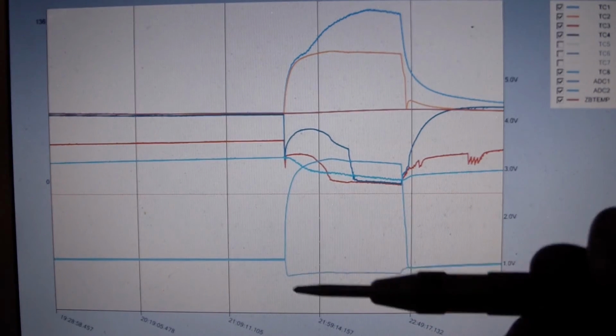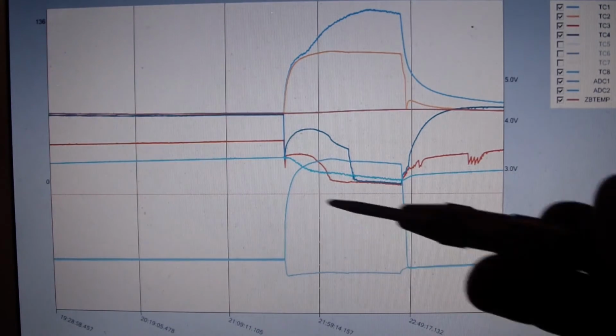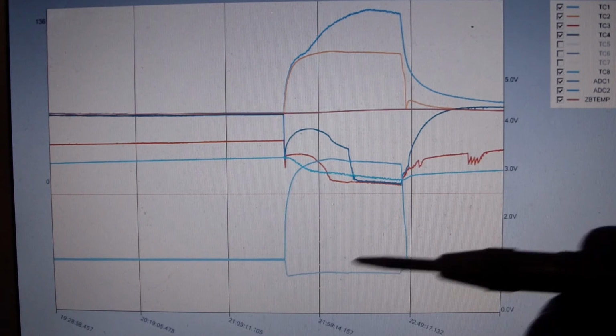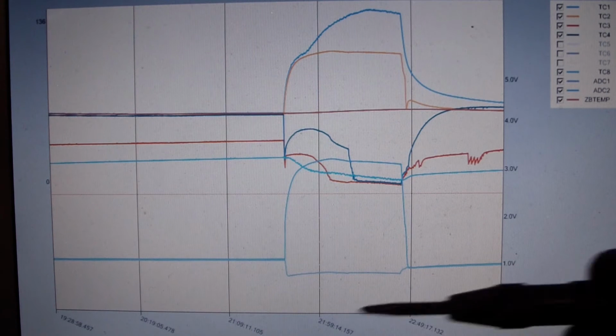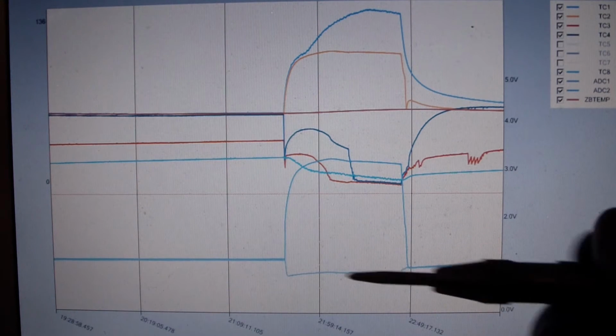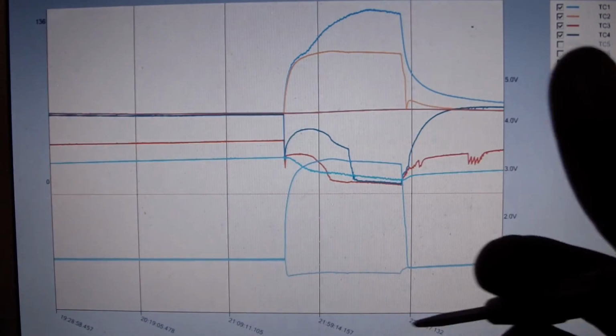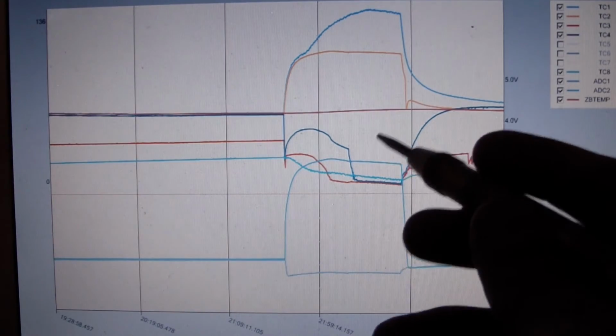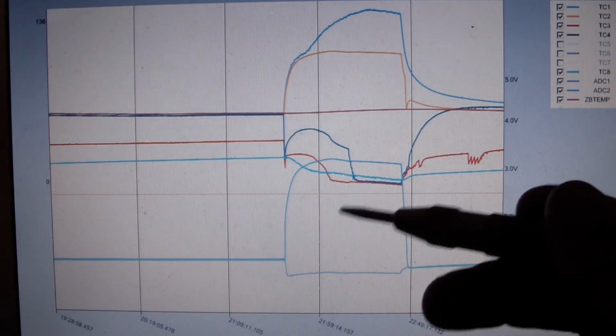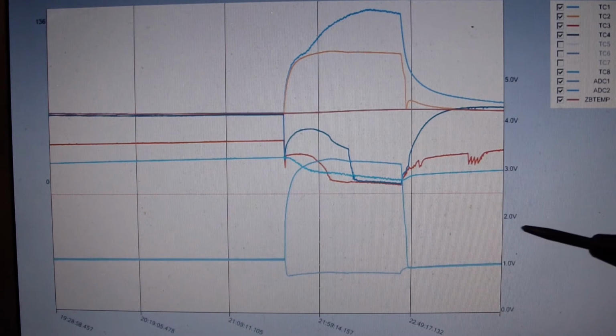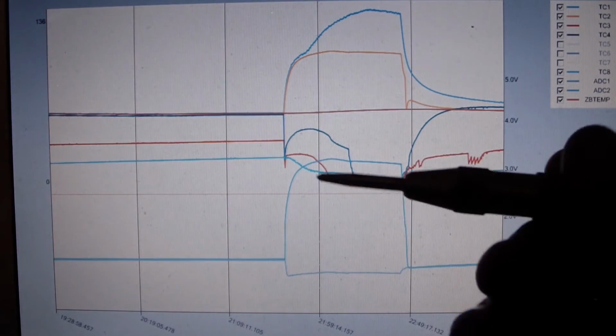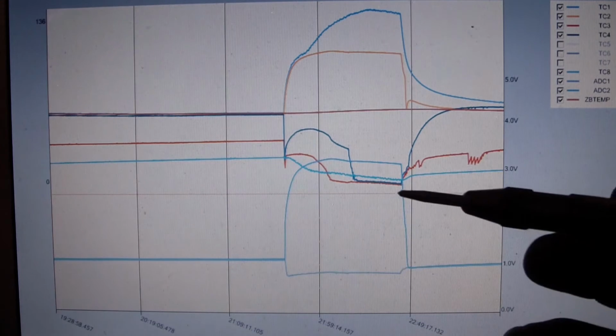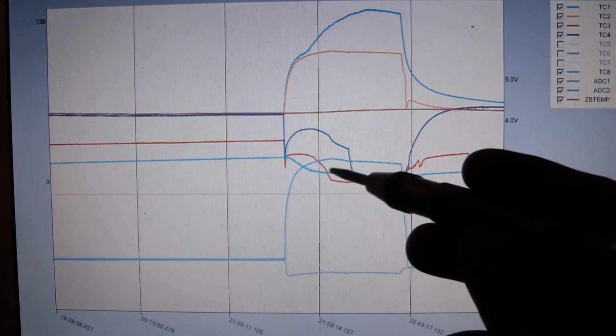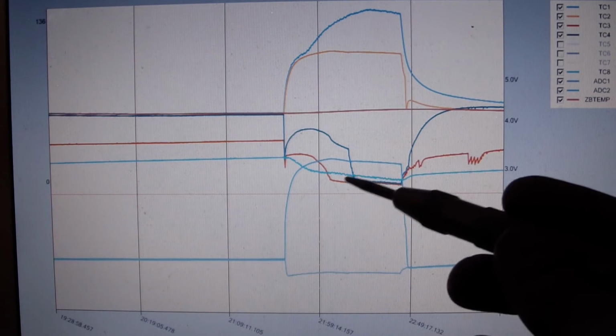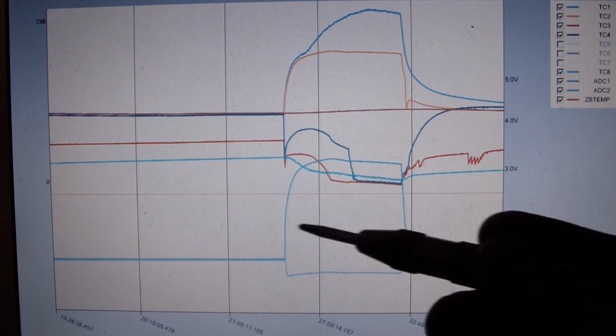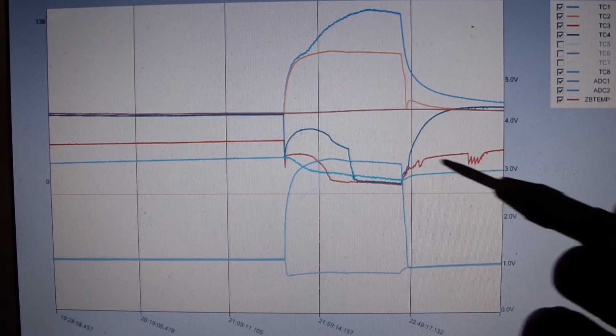because that water is going to start to freeze back to ice. It's going to form an insulative barrier around the copper tubing, and so the thermal conductivity across this layer of ice and into the copper tubing, into the refrigerant, is going to be reduced. As this insulative layer grows larger and larger, there's going to be less violent boiling of the liquid refrigerant in the low side. So given a given amount of flow of liquid refrigerant into the evaporator, at the beginning of the cycle it might not be enough, but towards the middle it might be plenty, because the capacity of the evaporator has been somewhat diminished.